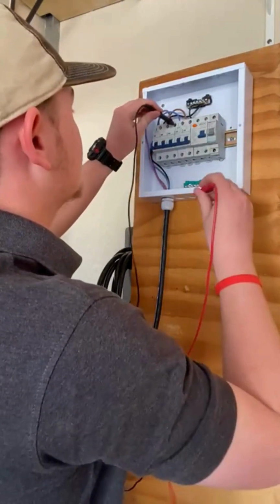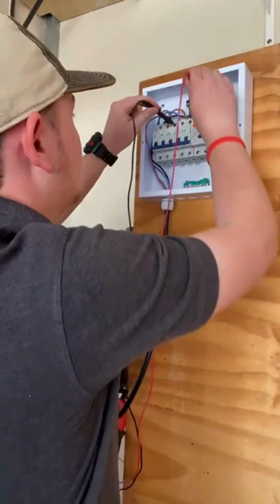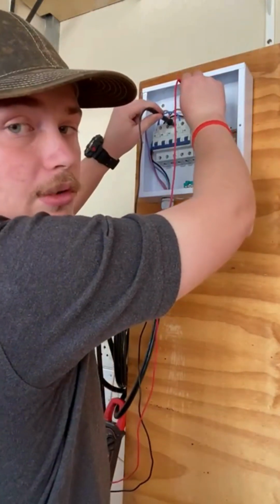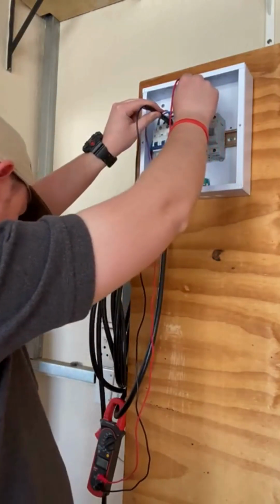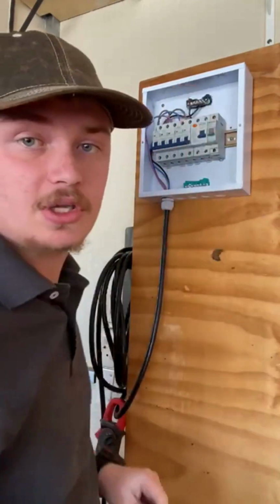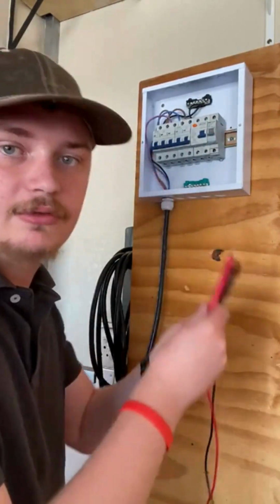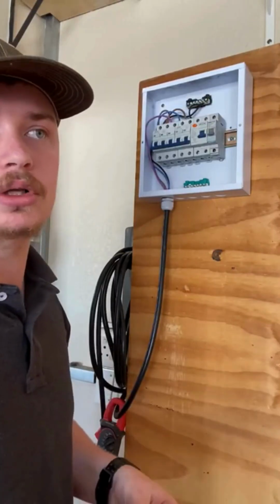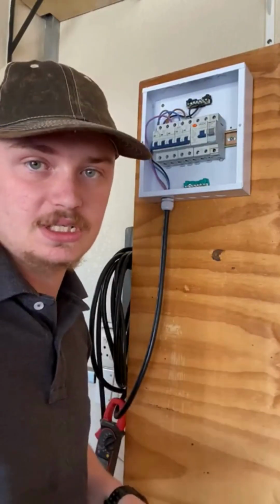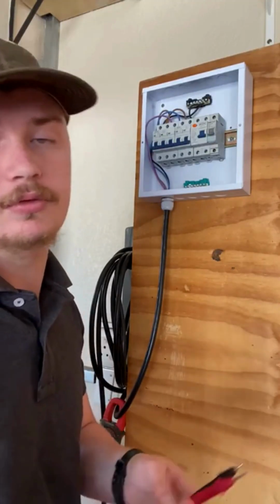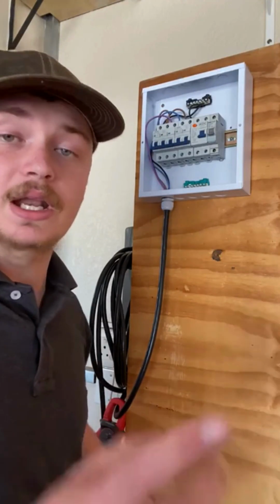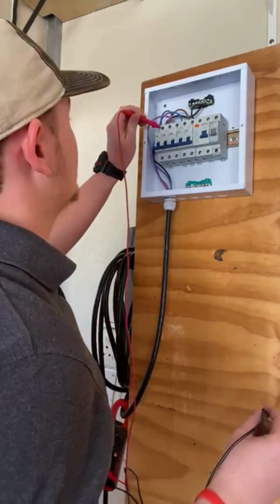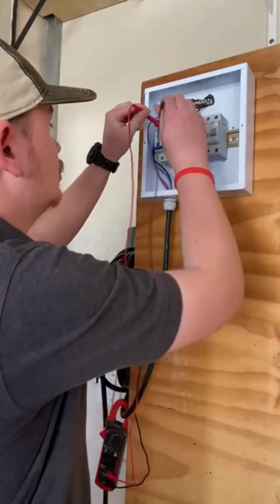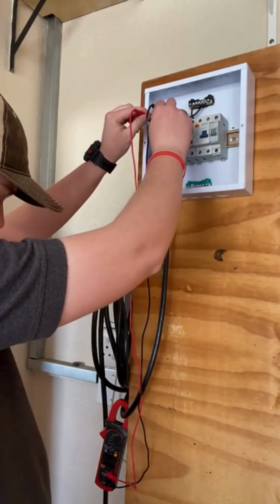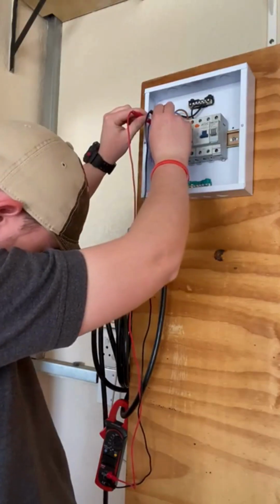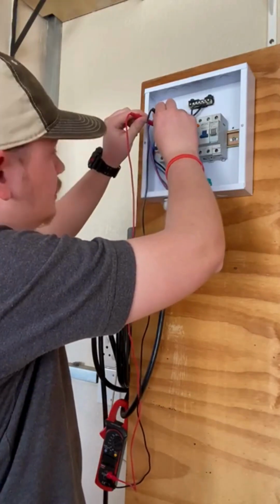If we measure L3 to neutral, we get 238. So one live to neutral will give you about 230 to 240 volts. Now we're going to measure between phases. If we measure L1 to L2, what we're getting on the multimeter is 408 volts.